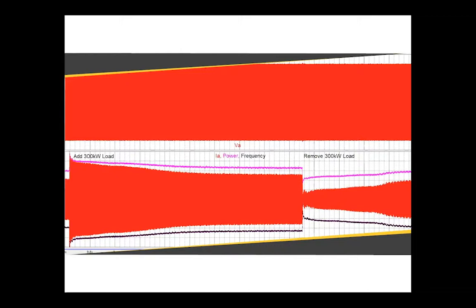So here we had about a 500 kVA generator, so we would add 300 kilowatts of load, and then later we subtracted it. The timeline here is about 35 seconds. The small divisions are half a second, and the bolder divisions are 2.5 seconds. So you can see that as we added load, the inverter was able to grab the load that was necessary. You can see the voltage up above. You don't see a problem. There may have been a little dip there that's been run over. But then as we drop the load, you can see just the tiniest little disturbance up above and below where we have a little bit of an overvoltage, but as you can see, that's a pretty minor overvoltage and very short.